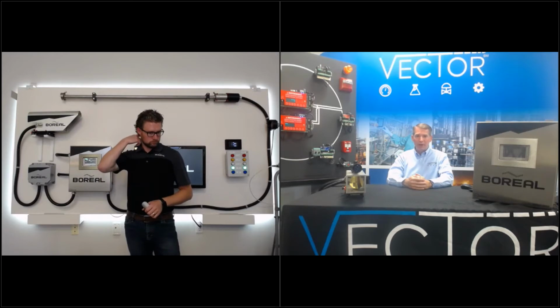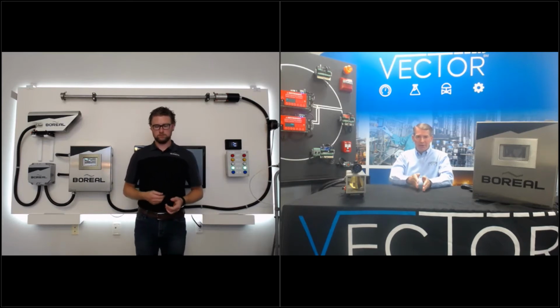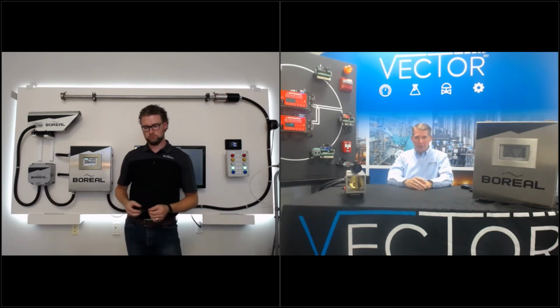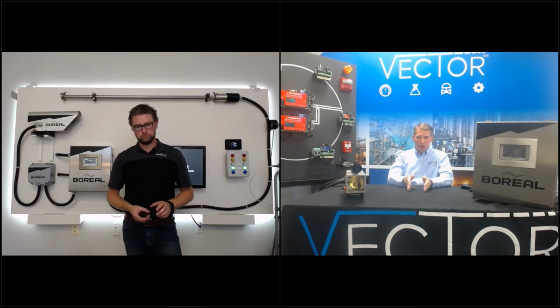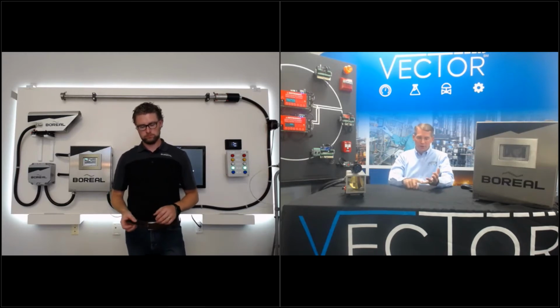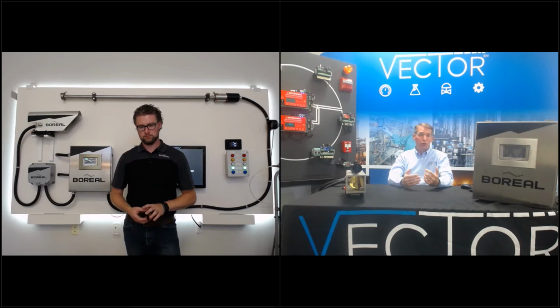You saw how quick and easy it was. It responds really fast. So not only is it pretty much maintenance free, but if you need to do any testing or calibration with a test cell, the time required to do so is greatly reduced from walking around with bottles of gas, calibration cups, making sure you've got the right regulator. So there is a cost reduction there as well. No bottles of gas to keep using and go from instrument to instrument. Truly it is also a one-person verification. No need for multiple people to be pulled away from something else in the facility to maintain this device.